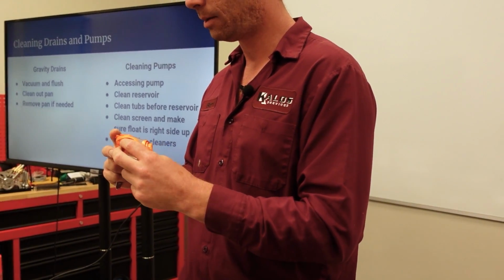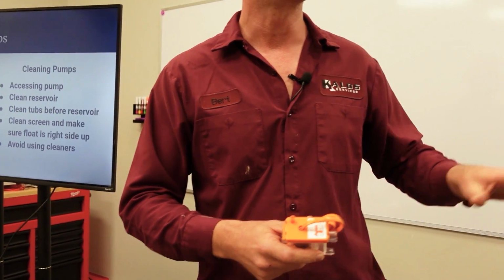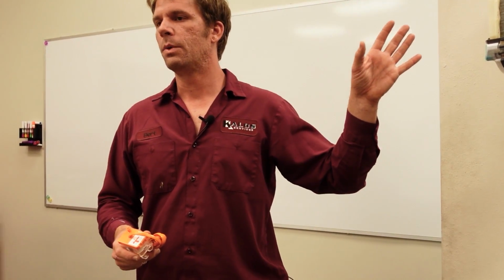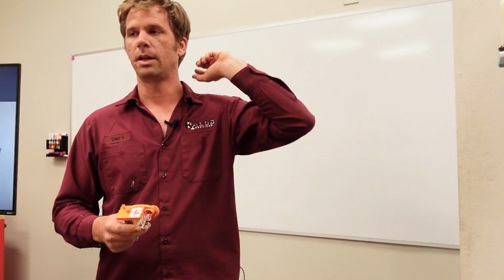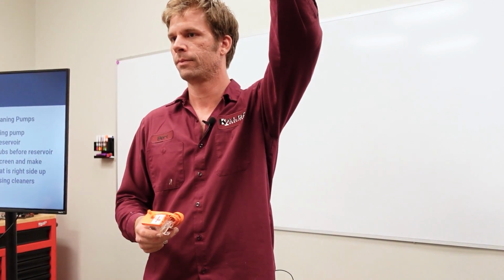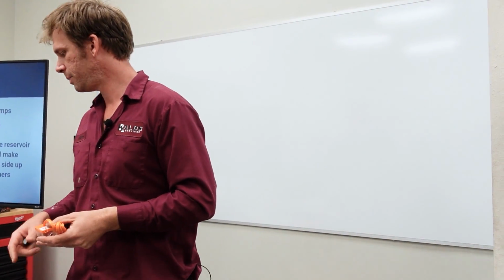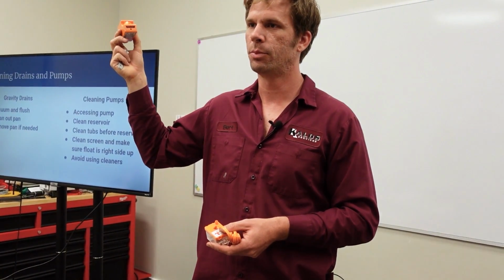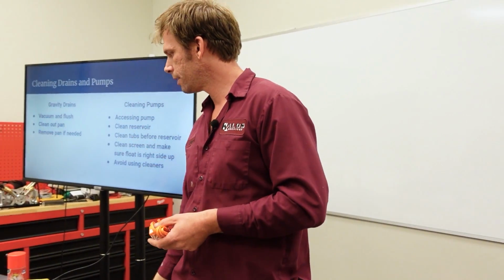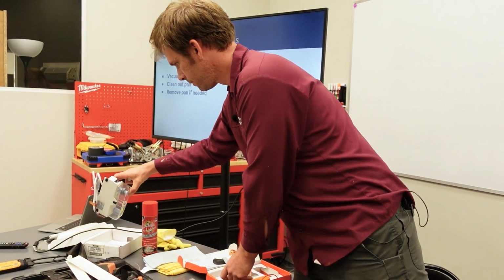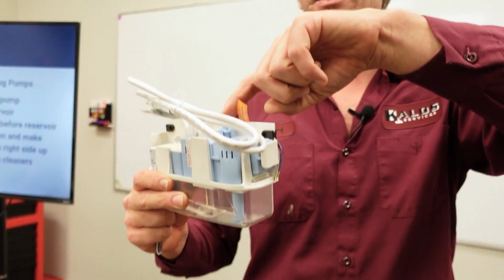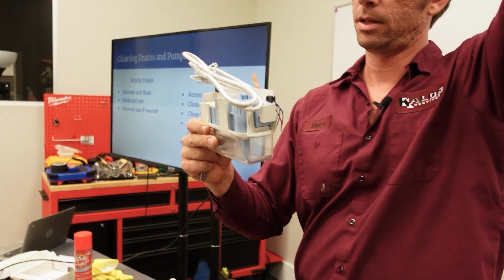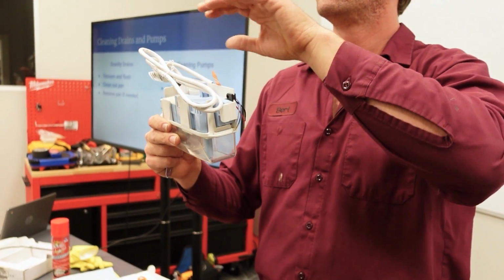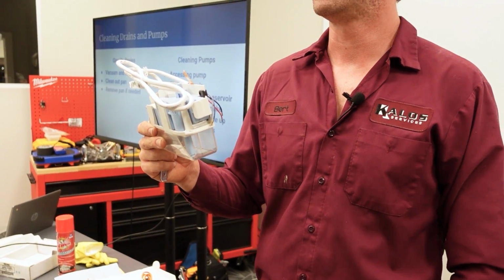Now, if you're running into repeated pump issues, or you've noticed that there's a lot of algae in your system, then I would recommend hooking up to your line that actually goes outside and blowing that out as well. So you're going to want to hook up that, and that could depend on application. If you have some motor that's in the attic, only in a rare situation where I think my line's clogged am I going into an attic and opening it up and pushing air through that. But a lot of your pumps, like in this application, I'll show you cleaning this as well. You have that all right here, so then your exit pipe right here just goes up, connects to copper, and it goes downhill from there outside. And so you can unhook from here and push nitrogen through to flush that out a little bit better too.